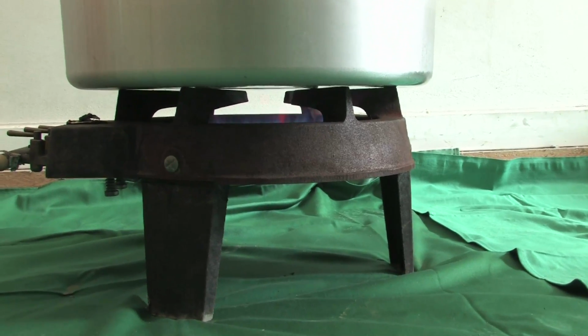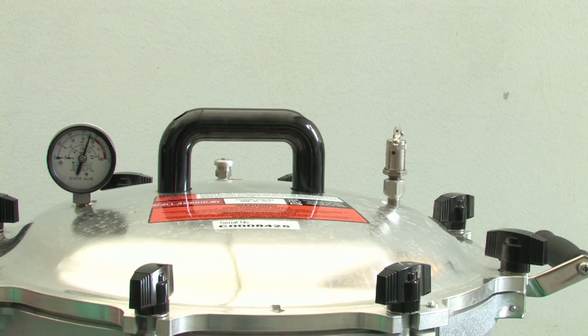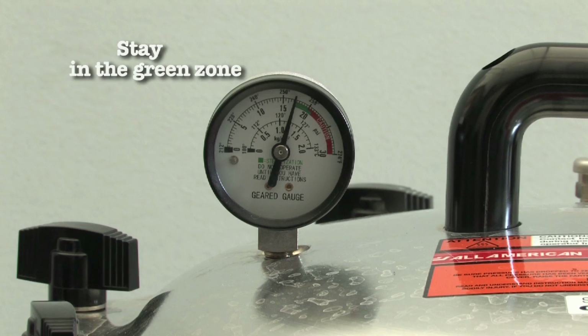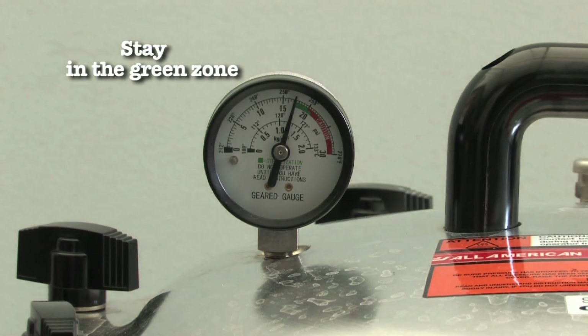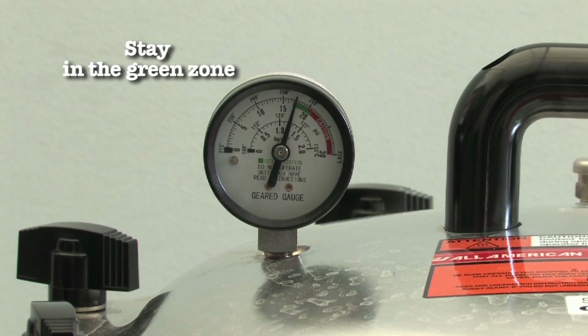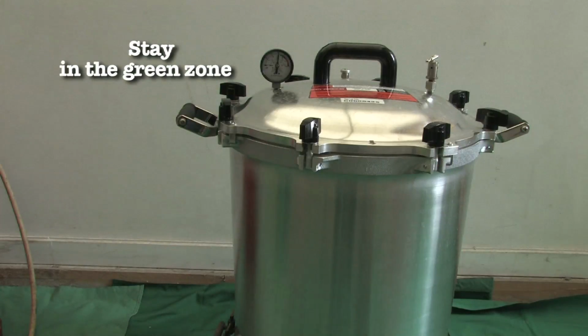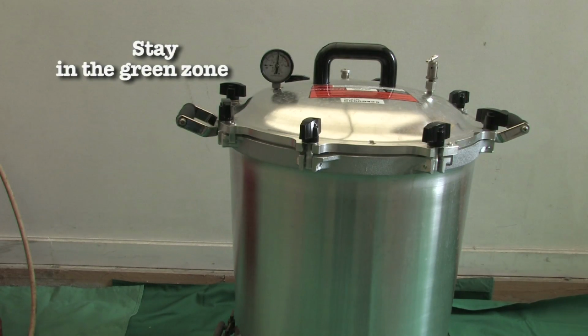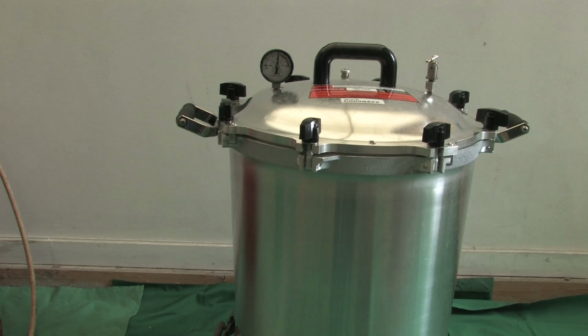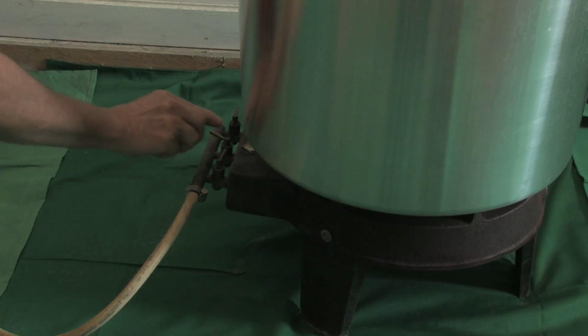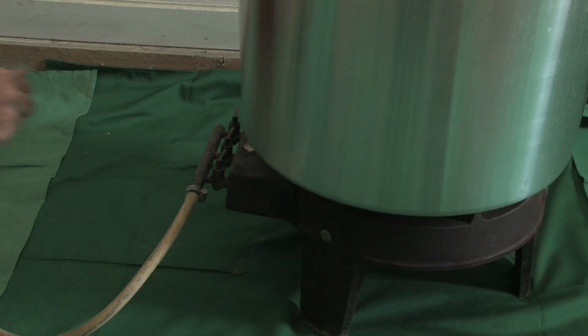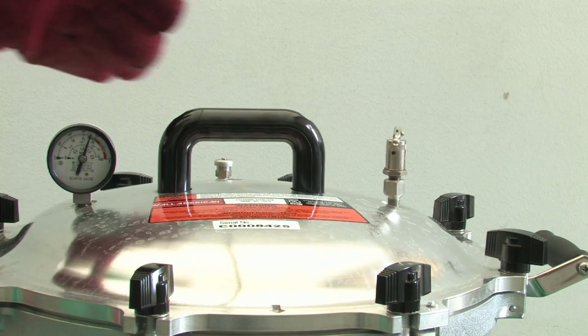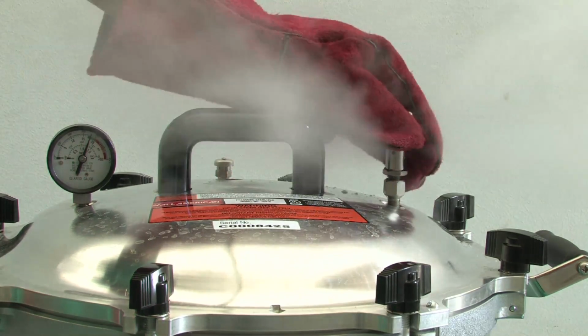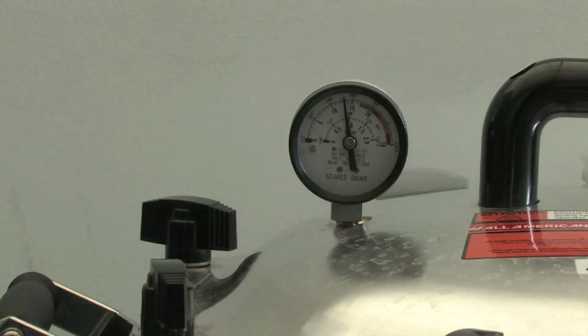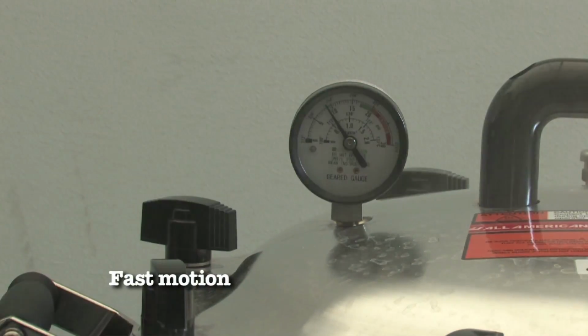Adjust the heat source so that the pressure does not go into the red zone on the pressure gauge, but stays in the green zone for a pressure between 1 and 1.4 bars, or a saturated steam temperature between 121 degrees Celsius and 127 degrees Celsius. 11. Drying. After 30 minutes, turn off the heat source. Open the valve to let some of the steam escape until the pressure drops to 0.2 bars.